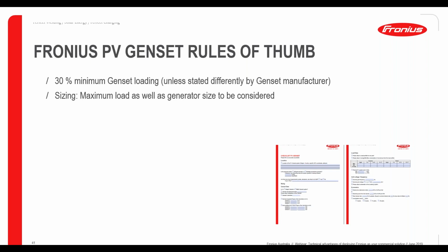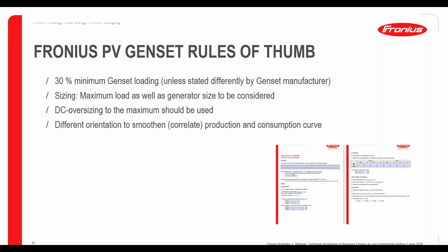That means the size of the solar system is not a case of filling the entire roof or the entire field with solar, but it should be matched in priority with the generator in question. In terms of the DC to AC oversizing of the inverters you're going to have on site, the oversizing should be taken into account and maximized as highly as possible, as well as taking into account which orientation the panels are going to go in. For example, if you need higher loads in the morning, we're going to orient a lot of the panels to the east, and vice versa for the afternoons, to the west.